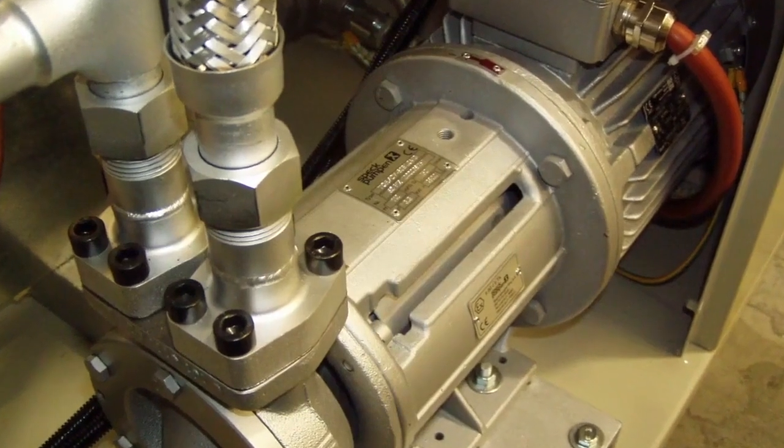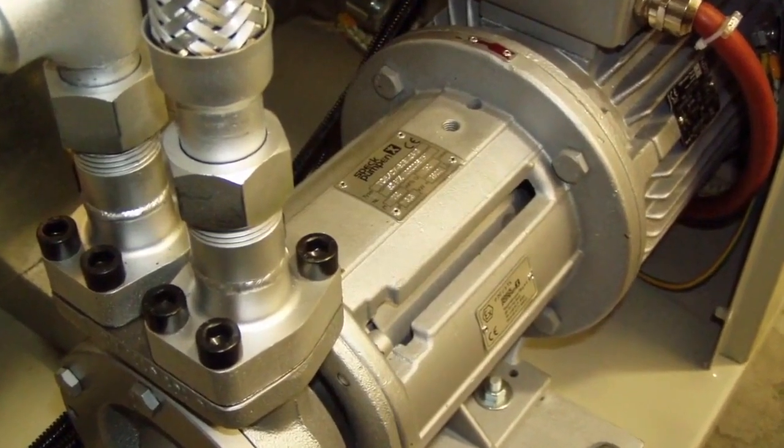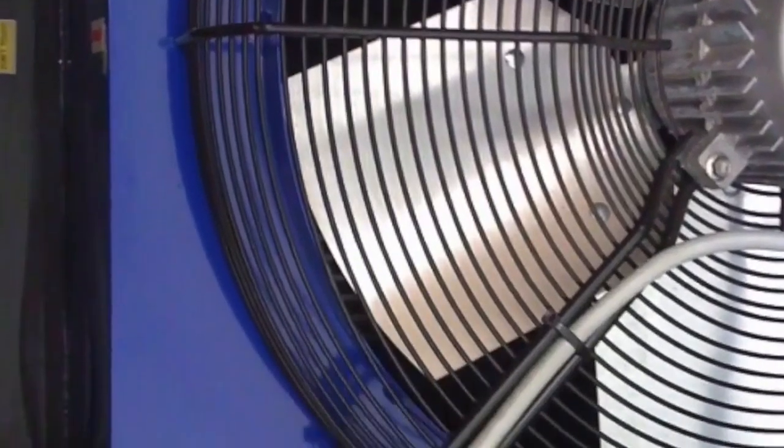The most straightforward approach typically involves considering the power of the pump motor that circulates the oil under pressure in the circuit. Because essentially this is the element that transmits thermal energy to the oil. Usually 30%, 40%, maximum 50% of the installed power of the motor of the pump that pressurizes the oil is calculated. This is the amount of energy that needs to be removed from the oil for cooling. It's an empirical calculation, of course.